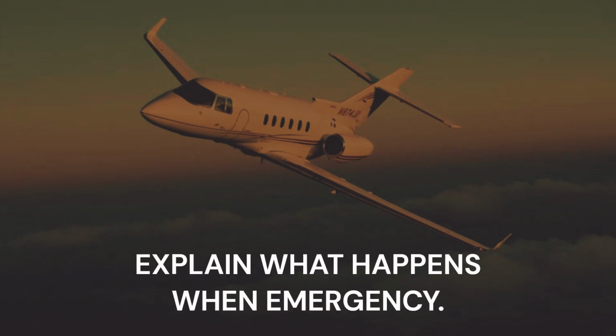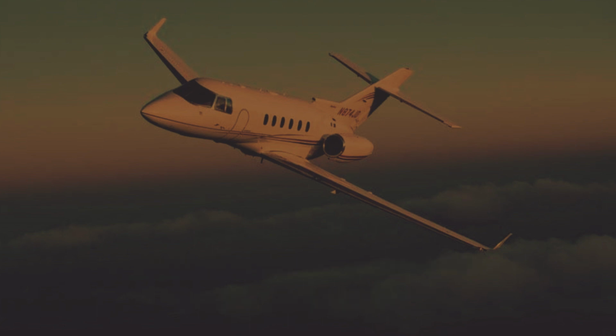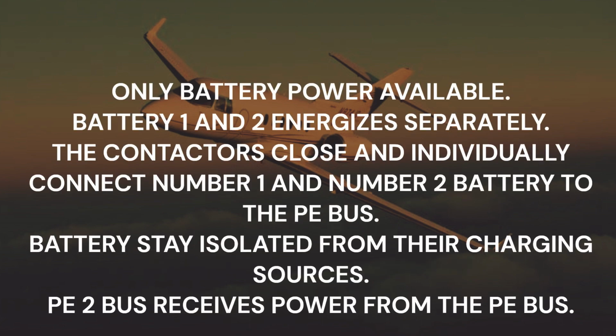Explain what happens when emergency. Only battery power available. Battery 1 and 2 energizes separately. The contactors close and individually connect number 1 and number 2 battery to the PE bus. Batteries stay isolated from their charging sources. PE2 bus receives power from the PE bus.